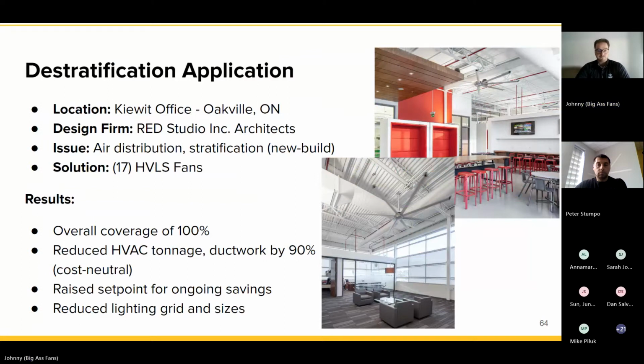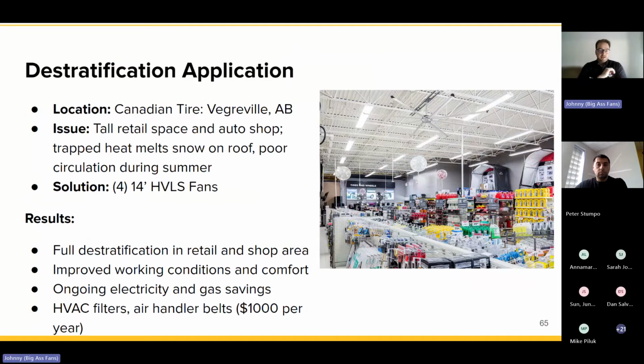Another good example, Canadian Tire, they use fans for destratification. And like I was alluding to, they actually found they were saving additionally on things like HVAC filters, maintenance, replacement belts — about $1,000 per year. So something you don't think about: you may be saving a couple thousand dollars on the gas side, but they installed 4 of these fans and were saving about $1,000 a year just on maintenance of their HVAC system, because it was running so much less. So really any application, especially as you get into tall ceilings, you're going to find usually a significant ROI and a good fit for products like this.